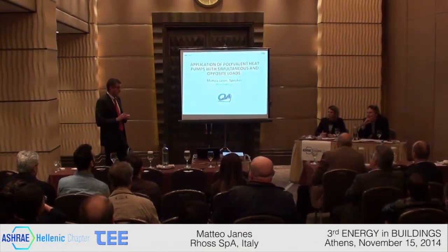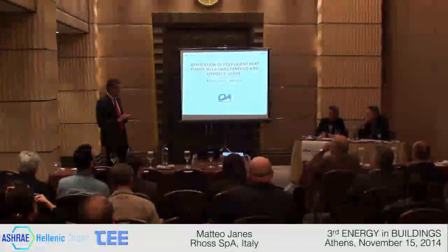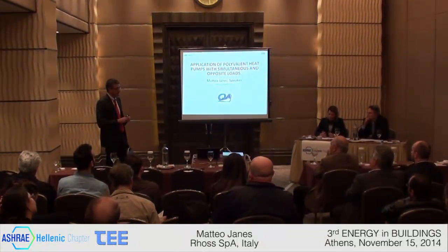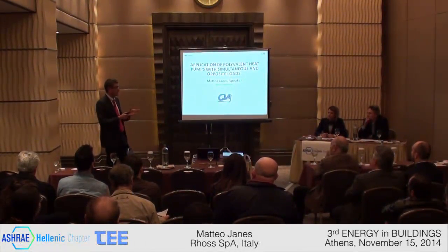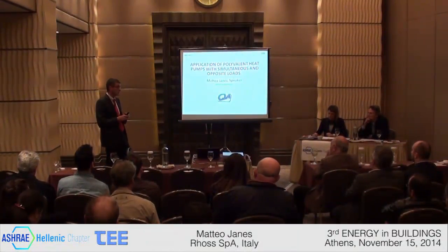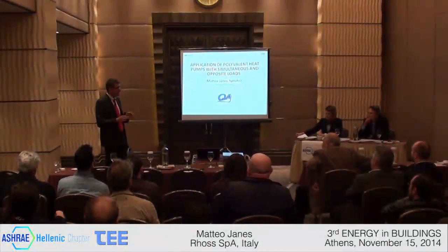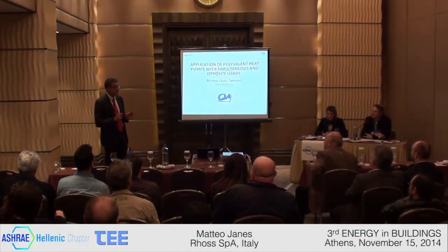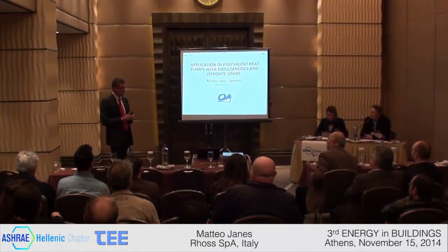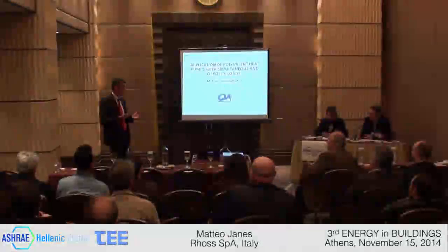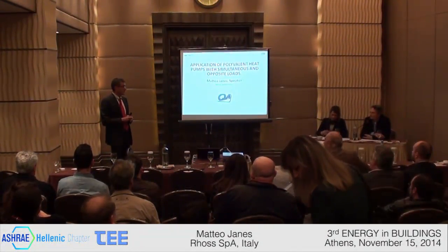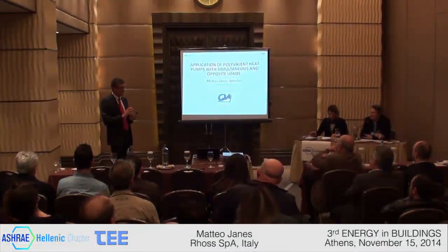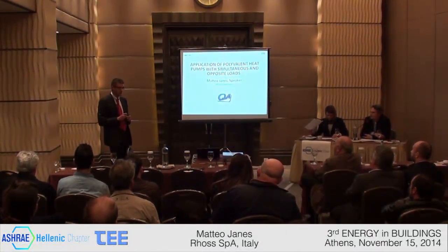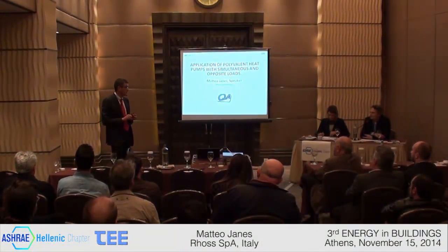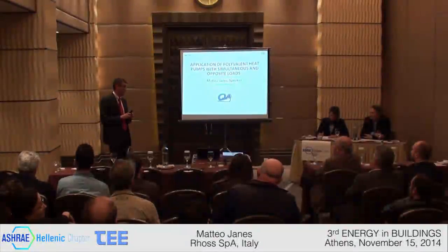Do you have any hard data on that? We've done a lot of research with this technology in our laboratory. A very critical factor for the success of this technology is the plant system in which the units are installed. A correct evaluation of the thermal inertia of the two circuits, the cooling and the heating circuit, can make the real difference between a system that operates poorly and a system that operates without any problem. If the combination of unit and plant system is not correctly designed, the electronics is the first part of the unit that can suffer.